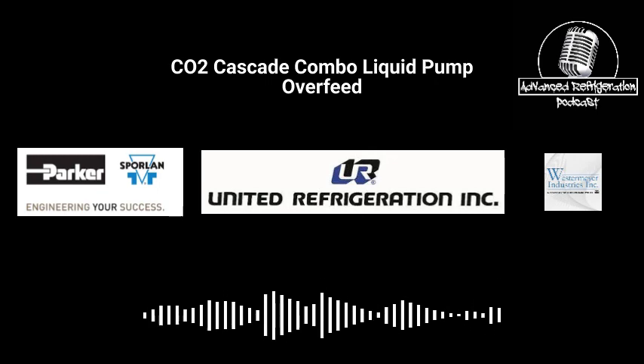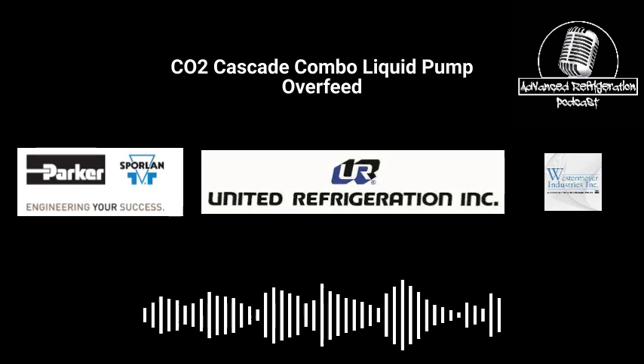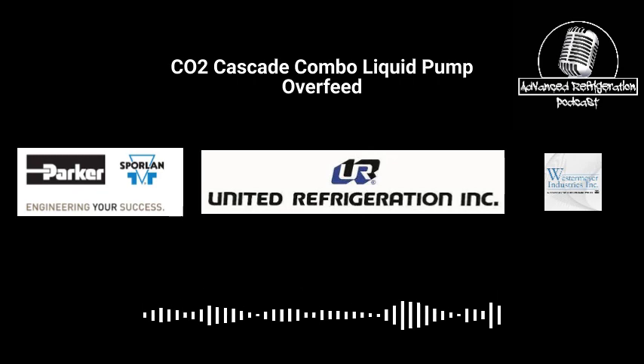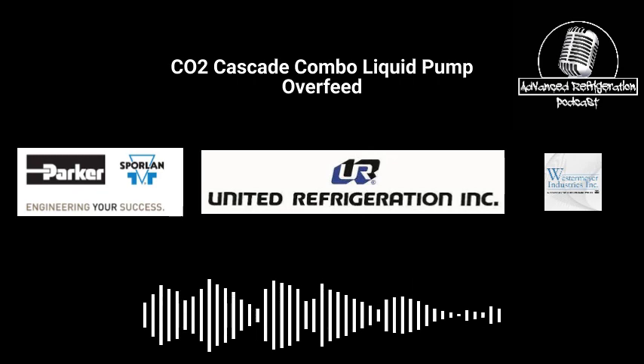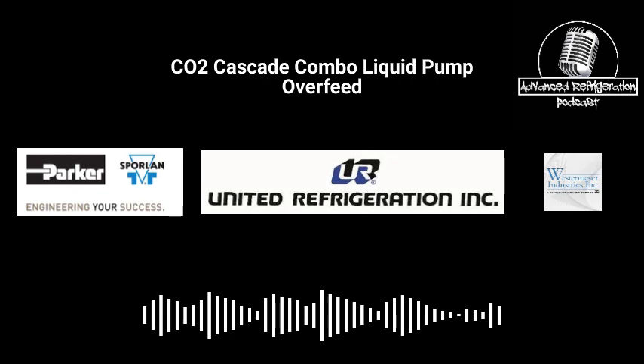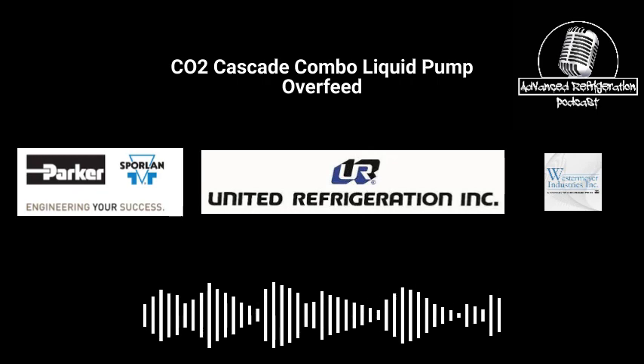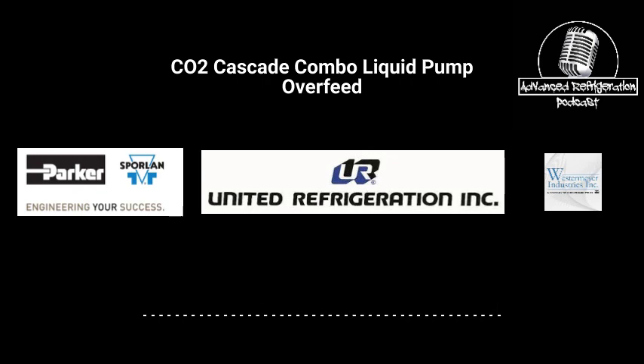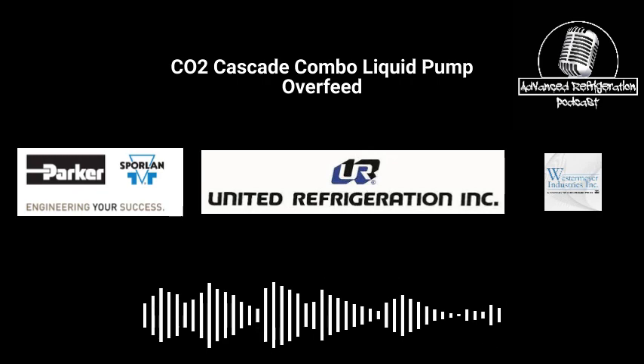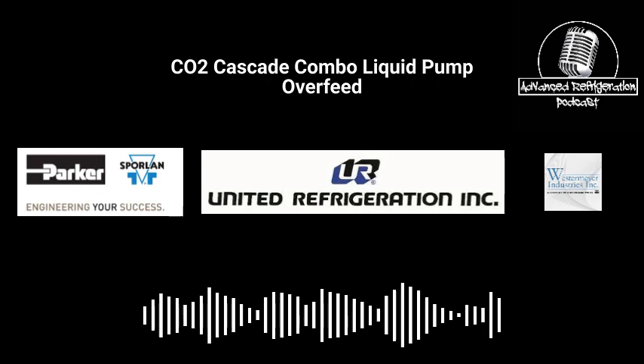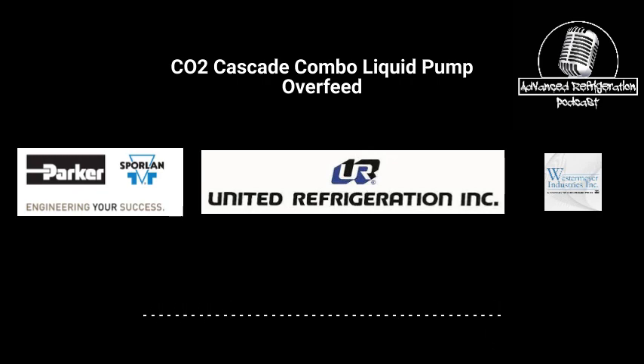They're starting to make other refrigerants. I think Honeywell came out with one or two. They're A2L, but the charge max is only like 260 pounds, and they run at different pressures. They said it's comparable, almost like 134A or R12 pressures. So even if you wanted to convert something, you couldn't, because you'd have to change out your piping and compressors. All your velocities are messed up. Pretty much stuck.